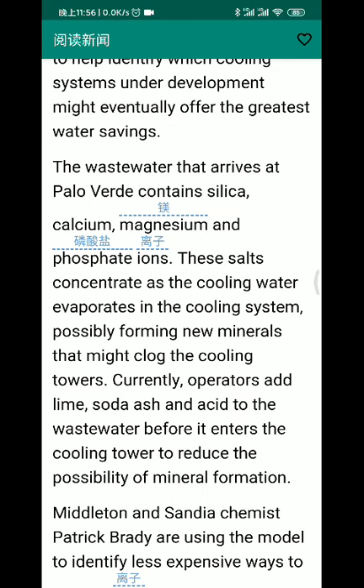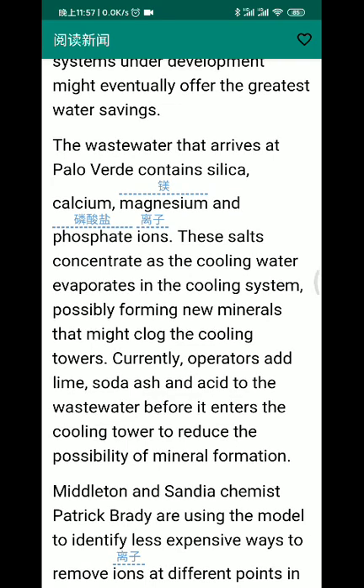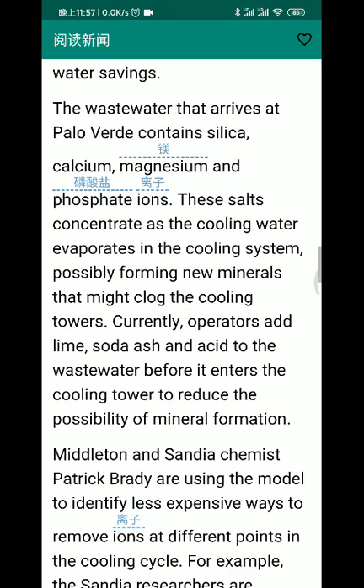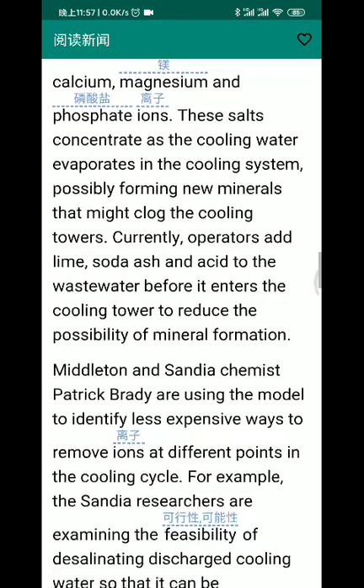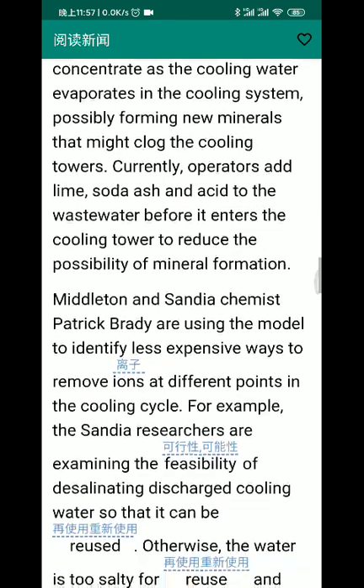Currently, operators add lime, soda ash, and acid to the wastewater before it enters the cooling tower to reduce the possibility of mineral formation.